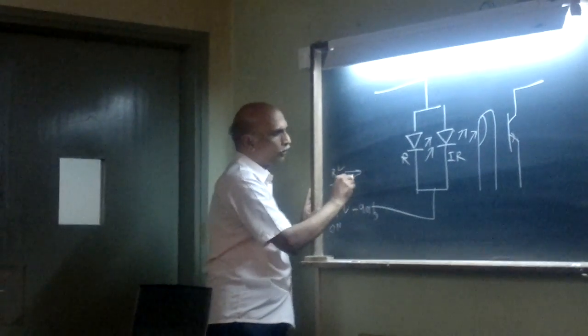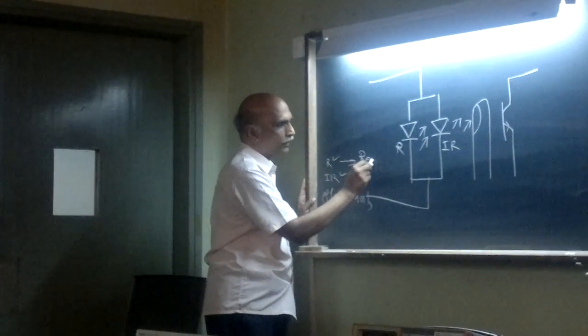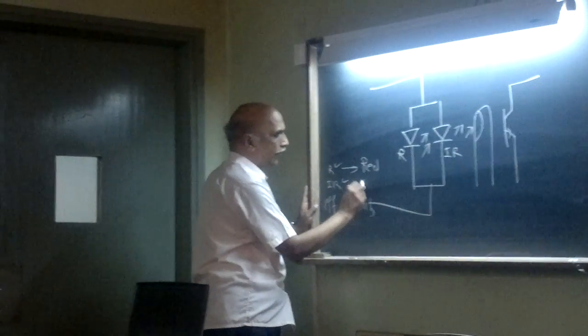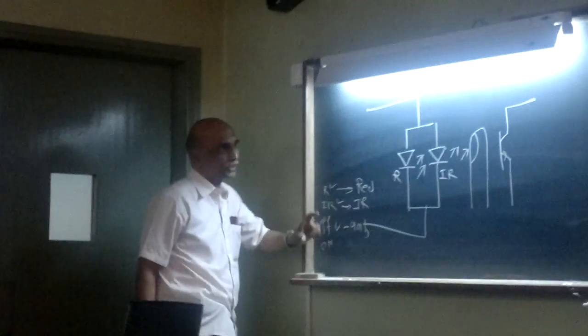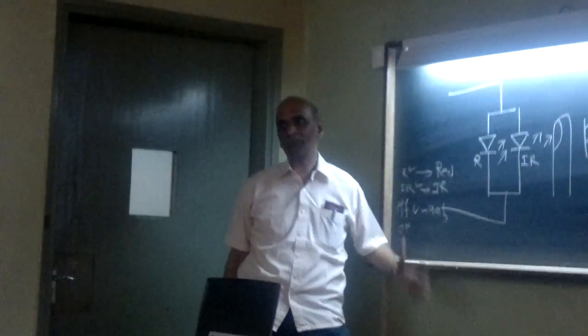When the red is on, you are looking at the output of the detector for the red element, and this is for the IR. So the detector is one, with an output for ambient, for red, or for infrared.